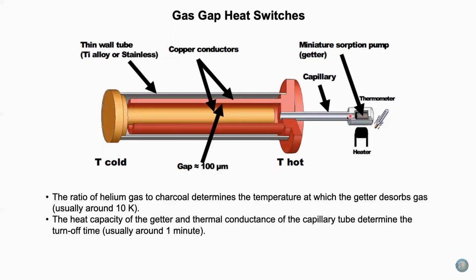You turn it on by heating up this little getter, which is a miniature sorption pump. We've got helium adsorbed here, and heating it forces the helium out into the gap, providing a thermal path from one end of the heat switch to the other. Turn off the heater, it cools down, and the helium is adsorbed again.